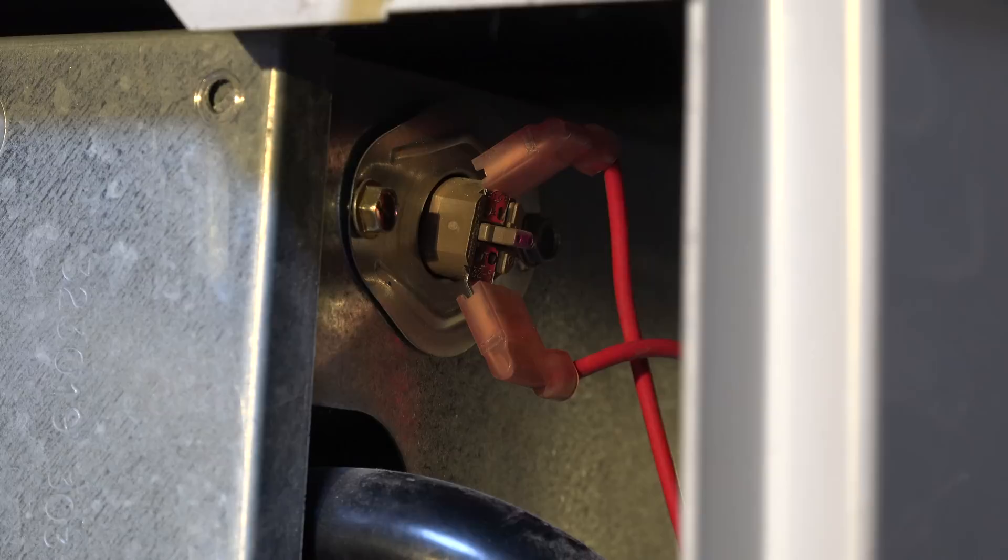Limit switches do fail, but I'm really concerned about rollout switches when I see one that has been replaced with a non-factory switch. Rollout switches are very important safety devices for furnaces and should not be replaced with anything other than factory switches. Okay, that's it on rollout switches.